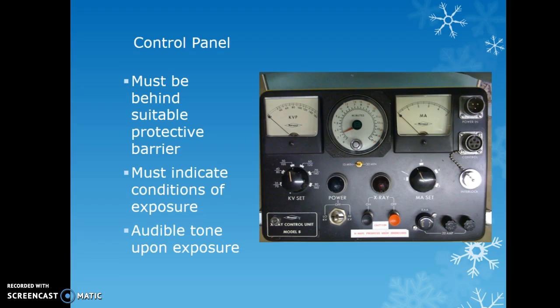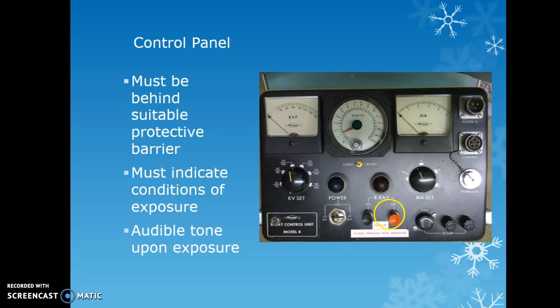The control panel must be behind a suitable protective barrier — generally outside the window of the room — so personnel don't receive unnecessary exposure. It must indicate conditions of exposure, showing KVP and mAs. There must also be an audible tone upon exposure. Newer equipment will have a visual indicator as well, usually an x-ray symbol that lights up, so you should listen for the audio and look for the visual cue.